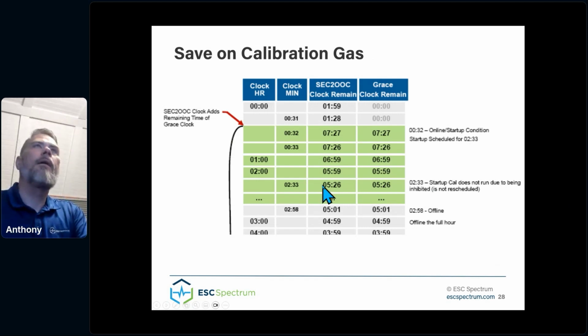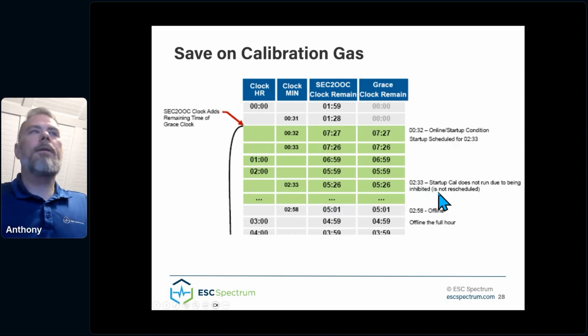So here's an example of that. And what we see here is a timeline put together. Now, there are a lot of these in the manual, and I'm going to talk about it in just a minute. You can see here that gray represents offline. So here's where the online startup condition occurred. There was a startup calibration scheduled. However, there was an inhibit pattern that evaluated true that prevented the startup cal from running. And you can tell by the SEC2OOC clock here, this is the math SEC2OOC function, that the calibration did not get rescheduled. I think this was actually verified in the MDI status, which I'll show in a minute.